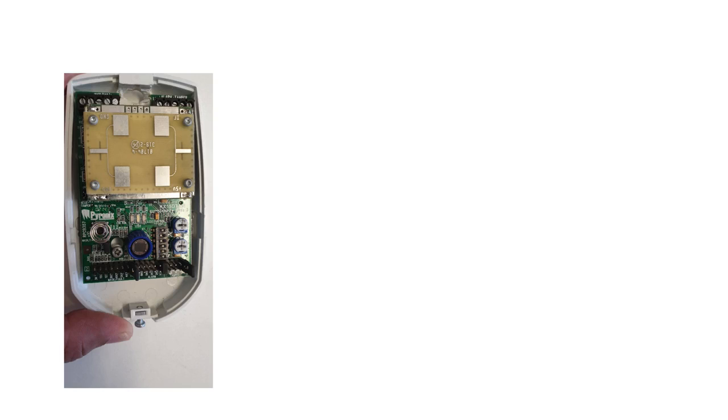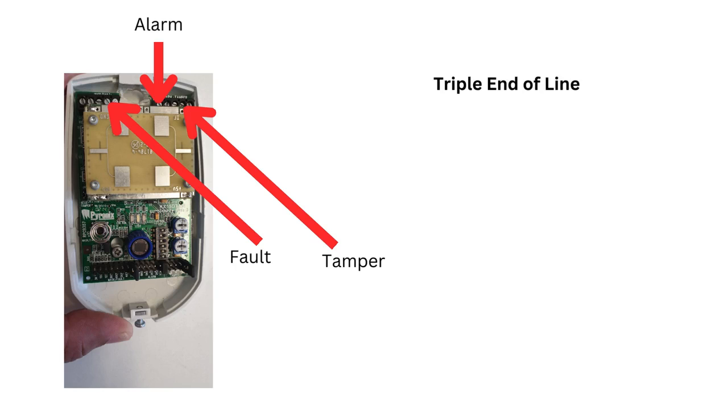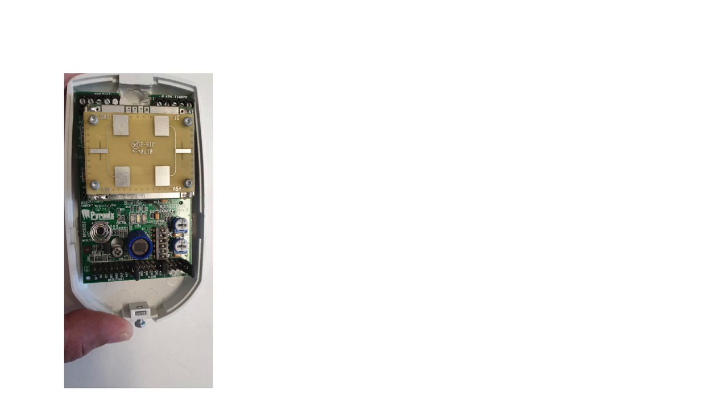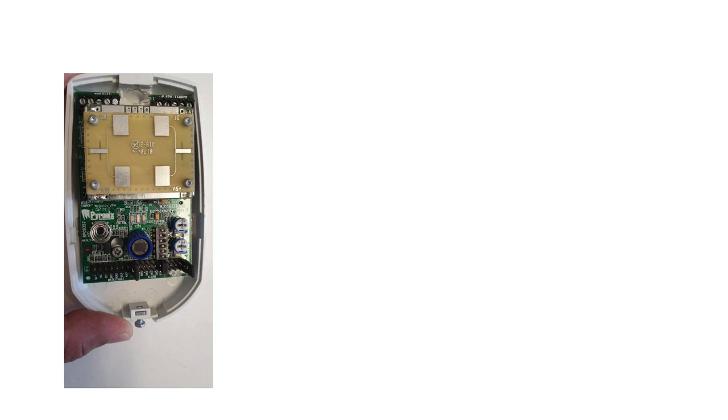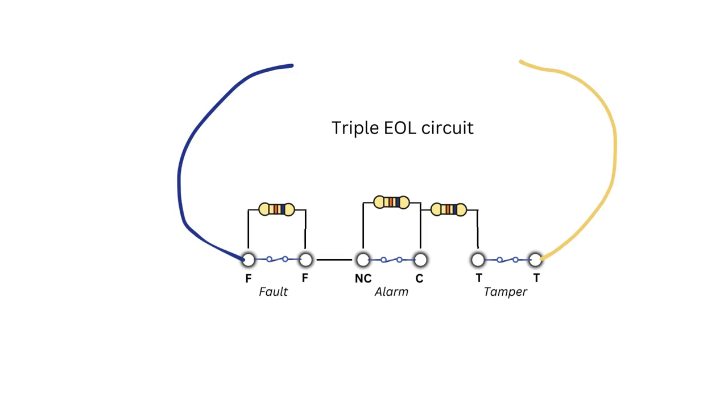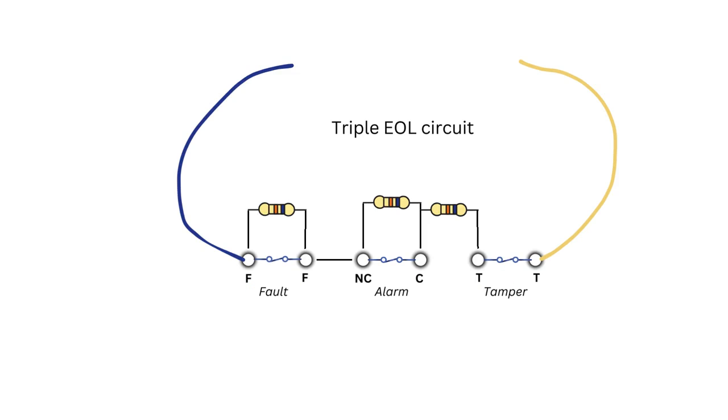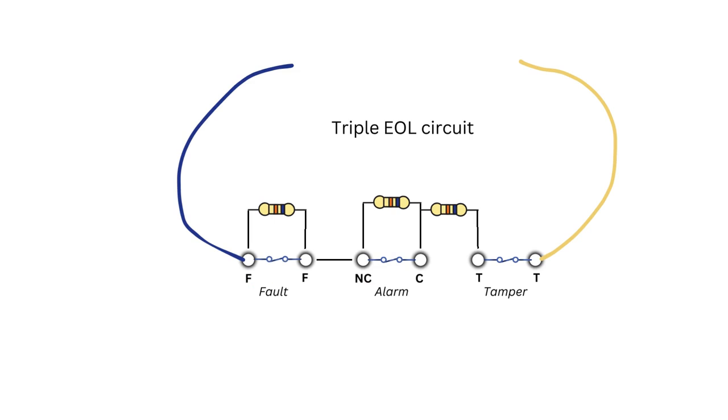In Grade III intruder alarm systems, security is paramount. These systems require advanced features for enhanced protection, and the triple end-of-line circuit plays a crucial role in this setup. Unlike simpler alarm circuits, the triple EOL circuit incorporates three separate resistors. Each resistor has a specific value, and they work together to monitor the integrity of the circuit. If the circuit is tampered with or compromised, the resistance values change, triggering an alarm.